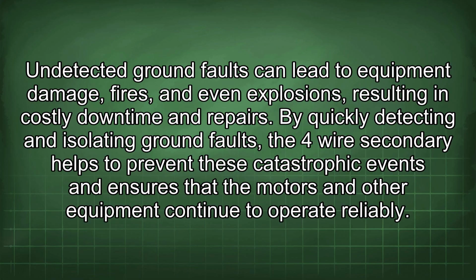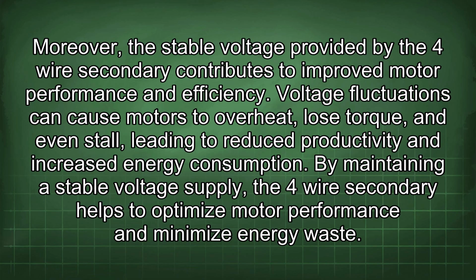By quickly detecting and isolating ground faults, the 4-wire secondary helps to prevent these catastrophic events and ensures that the motors and other equipment continue to operate reliably. Moreover, the stable voltage provided by the 4-wire secondary contributes to improved motor performance and efficiency. Voltage fluctuations can cause motors to overheat, lose torque, and even stall, leading to reduced productivity and increased energy consumption. By maintaining a stable voltage supply, the 4-wire secondary helps to optimize motor performance and minimize energy waste.